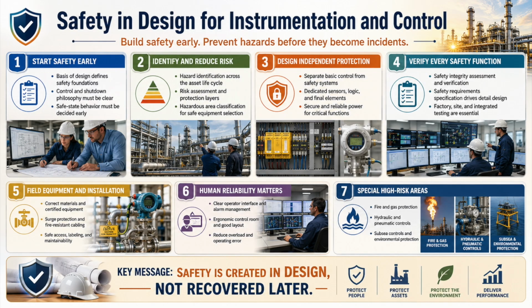Use continuous transmitters instead of simple switches wherever practical. A continuous signal reveals drift, disagreement, and developing failure. A hidden switch may remain failed until the exact moment it is demanded. Early warning alarms should occur before the shutdown point so the operator has a realistic opportunity to recover the process without defeating protection. Final elements deserve equal attention.